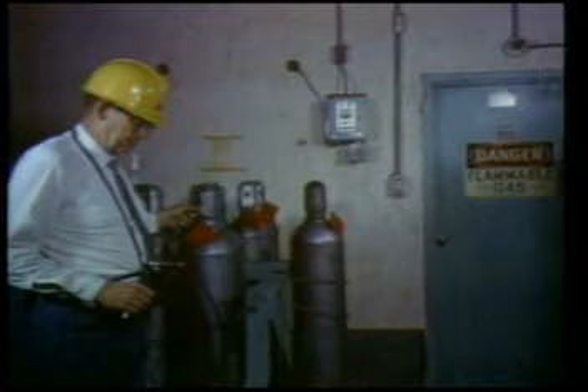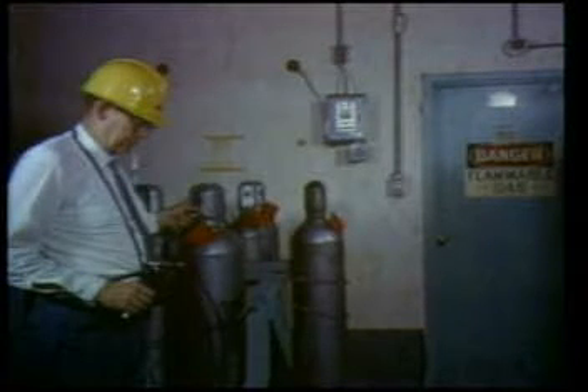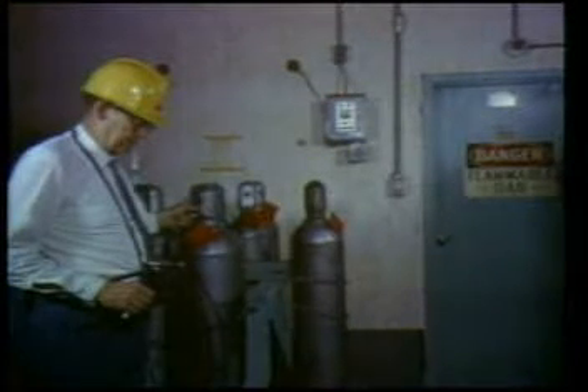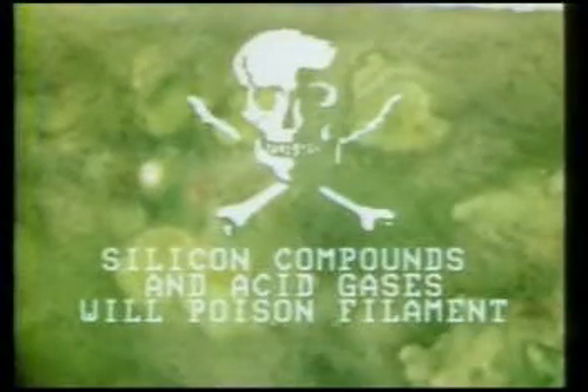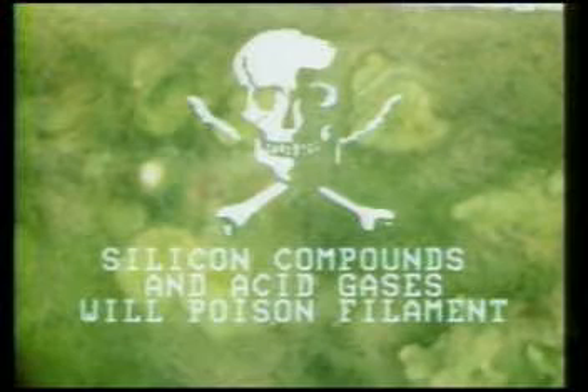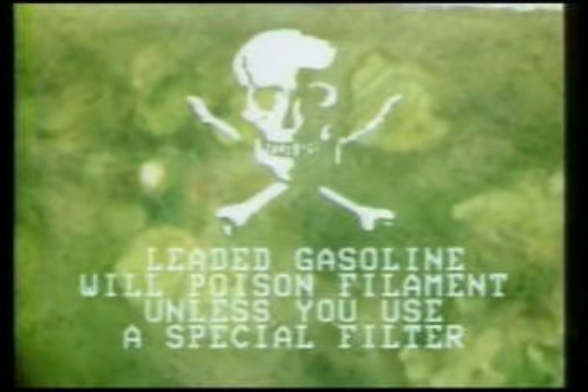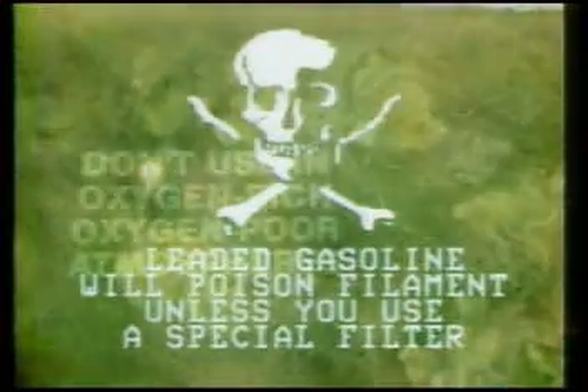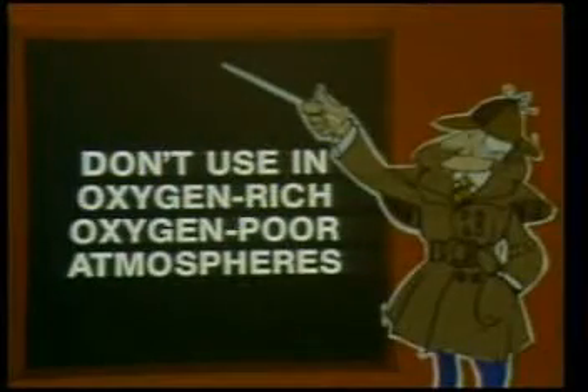The Explosimeter Model 2A can't be used under all conditions. For example, silicon compounds and acid gases will poison the filament, and it won't respond accurately. So will gasoline vapors, unless a special filter is used. The Explosimeter Model 2A should not be used in oxygen-rich atmospheres where there's more than 21% oxygen. And the Model 2A won't work in oxygen-deficient atmospheres either.